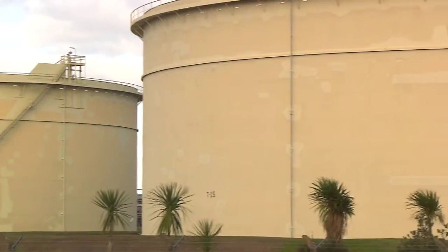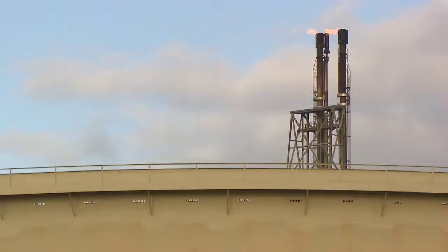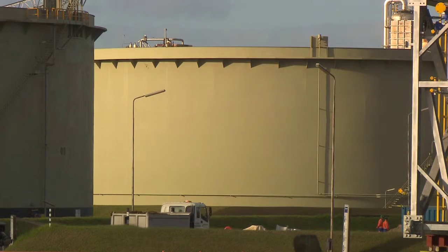Most growth and activity takes place where the fuel and water meet. The tank bottom fuel and water interface is the most obvious boundary. However, there are also considerable areas of interface on the interior surface of the tank shells.